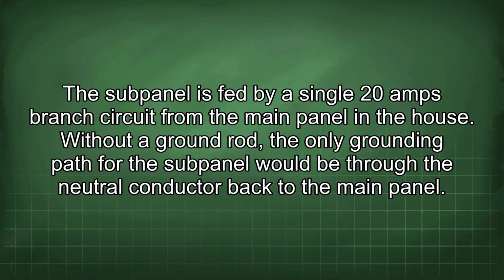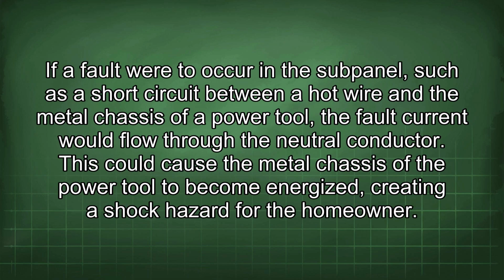main panel. If a fault were to occur in the subpanel, such as a short circuit between a hot wire and the metal chassis of a power tool, the fault current would flow through the neutral conductor. This could cause the metal chassis of the power tool to become energized, creating a shock hazard for the homeowner.